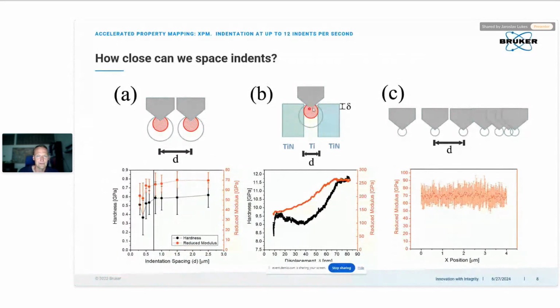If you have different phases which you want to map, you also need to keep your deformation zone local to measure just the intrinsic property of a single phase. If you want, you can also do a depth profile of mechanical properties. This is the depth profile of hardness and reduced modulus when you are indenting in between two different phases.